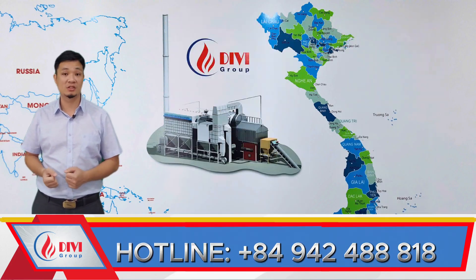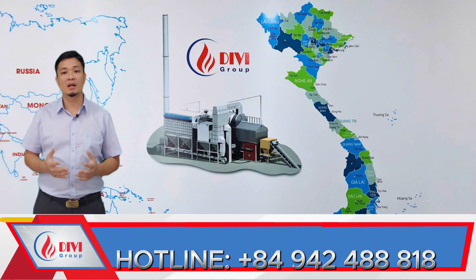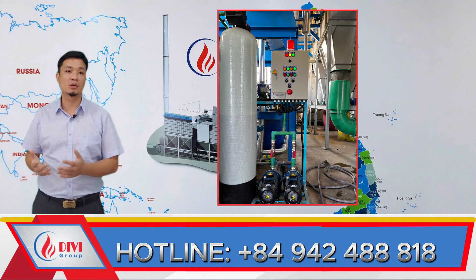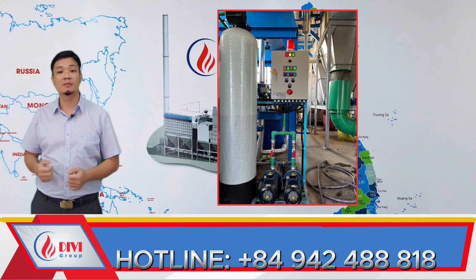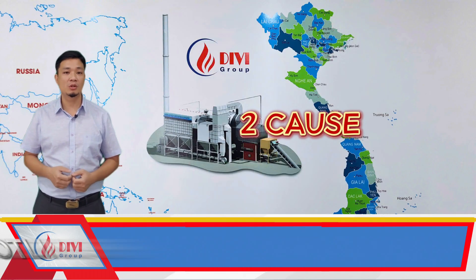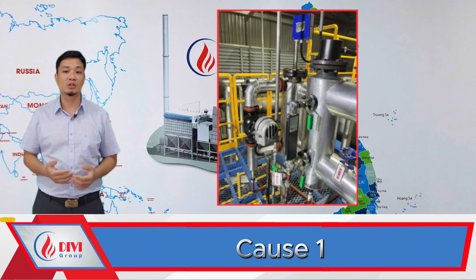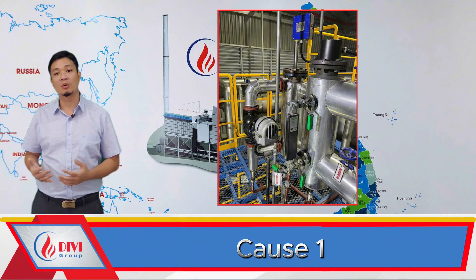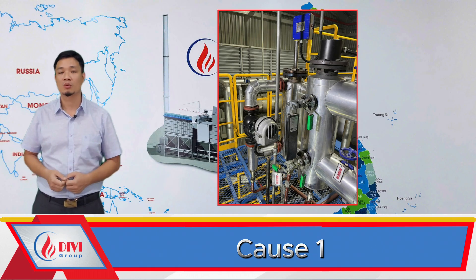Check the boiler water supply system. If the combustion system seems normal, the issue might lie in the boiler water supply. You might be supplying too much feed water compared to steam usage, or feeding water that's too cold into the boiler. Case one: excessive feed water volume. Possible cause — a faulty or inaccurate water level sensor. Too much water can lower pressure by overwhelming the system, carrying water into the steam lines, and triggering the feed pump to inject even more cold water.